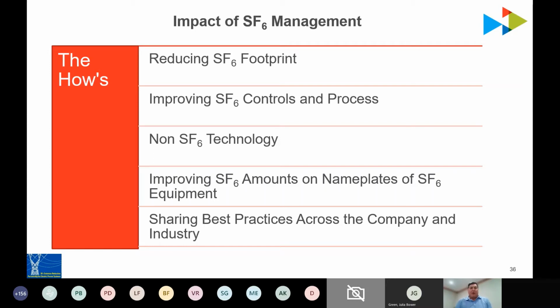The next bar, as we say, starts in 2016. We began to implement SF6-free clean air vacuum technology from Hitachi at 72 kV, limiting and reducing the footprint at that voltage class. It's been very successful - we have two operating companies with experience with that, approaching about 8 or 9 of those pieces of equipment in service, and it's performed really well.